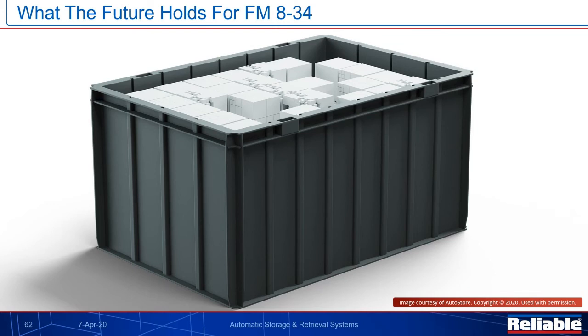What are the impacts of that in fire protection? Well, early indications are that it's not better than what we just talked about. It is potentially worse. And this is all very important and relevant because it goes back to the Ocado fire we discussed. The Ocado fire was a grocery warehouse, and one of the storage arrangements at that warehouse was ambient. The other one was refrigerated, and it utilized these non-solid walled bins. So we should expect to see guidance on how to protect that come out in a future edition. And like I said, indications are it's going to be worse than what we're seeing with this particular system that we just discussed.